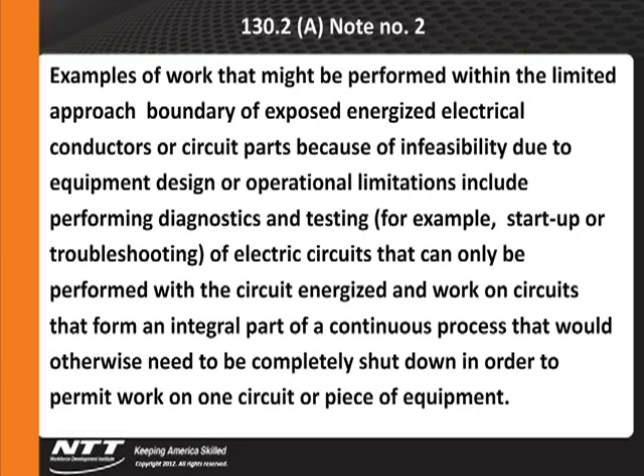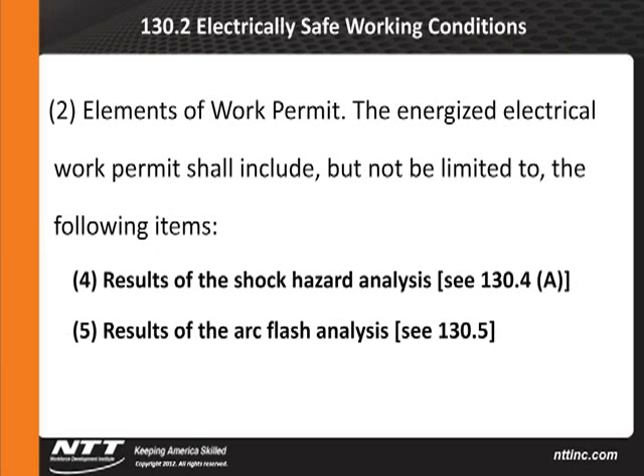So what are the elements that go along with this energized work permit? The energized electrical work permit shall include but not be limited to the following items. And it gave us the traditional three that were up there. But it also talks to us about we need to know what the results of our shock hazard analysis gives us out of the tables. It has to be the results of our arc flash analysis. So these are the kinds of things that have been added to that standard.